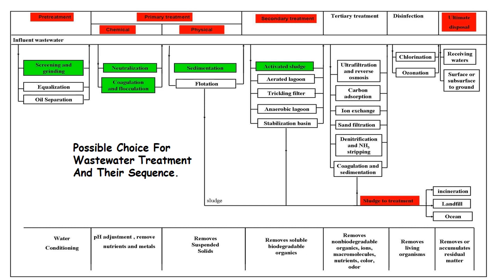This table summarizes the whole process of effluent treatment. At the top are the levels: pre-treatment, primary, secondary, tertiary, and ultimate discharge. Pre-treatment involves screening, equalization, or oil separation — conditioning the water for further treatment. In primary treatment, the chemical part involves neutralization, coagulation, and flocculation, which adjusts pH and removes nutrients and metals. The physical part involves sedimentation and flotation to remove suspended solids.